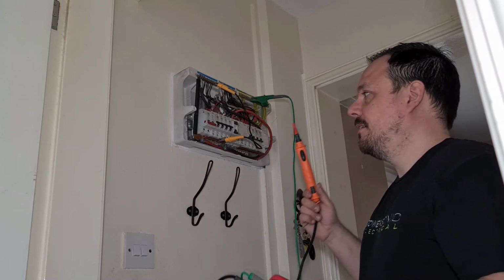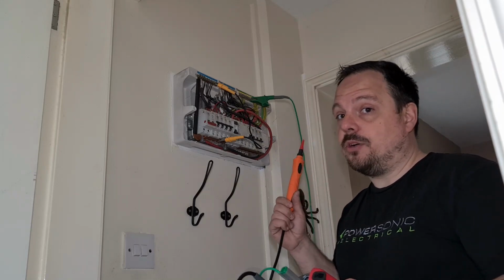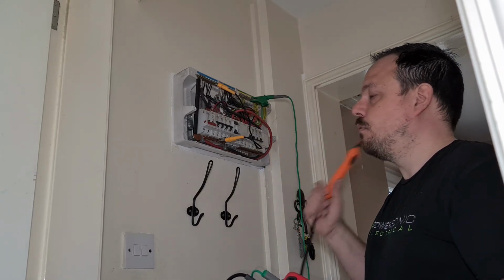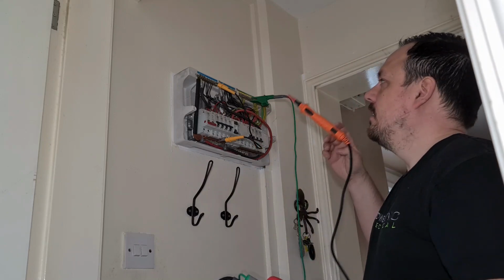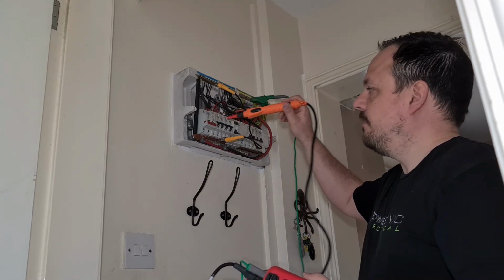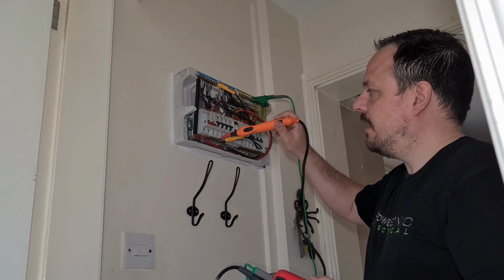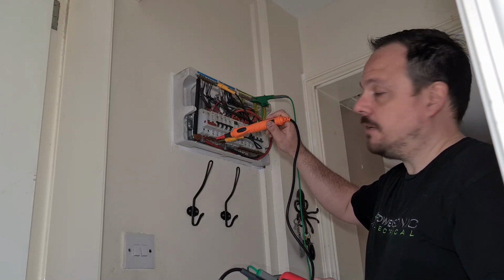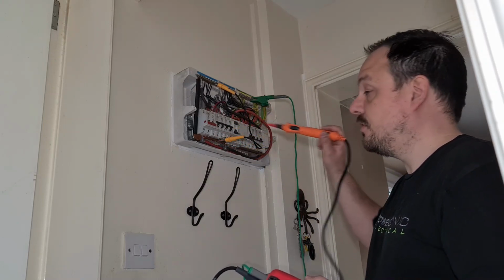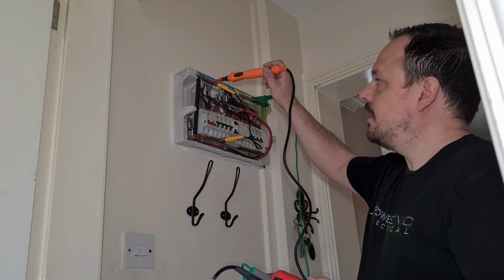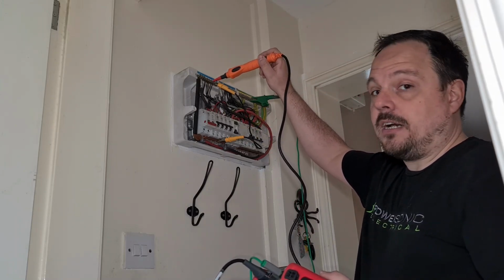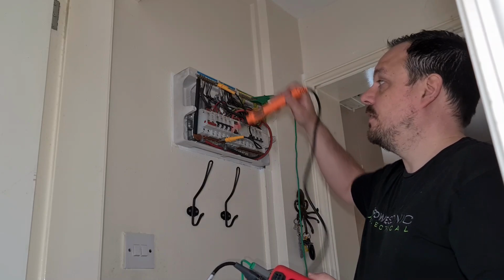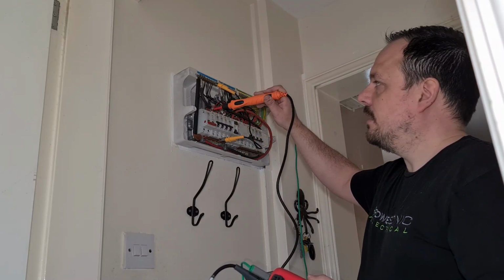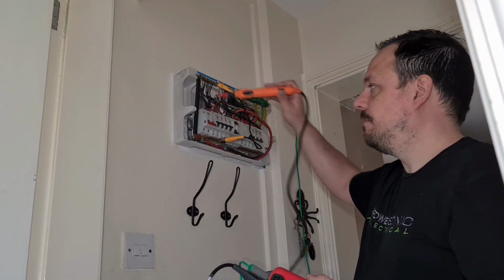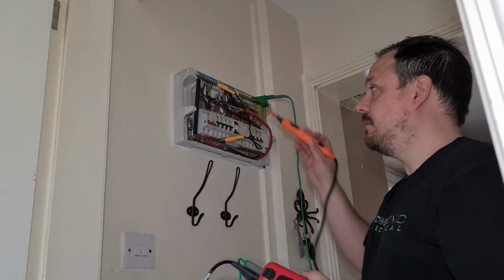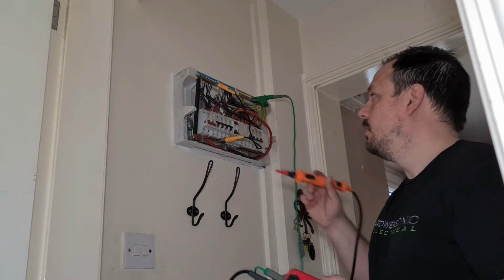That is where having a lock off away from the board you're working on is absolutely brilliant, and that's what I've got here. If we look through this, you can see what I've done. So the MCBs are in the on position, and I've got the little crocodile clip on the bus bar down here, just for those circuits. This is a split load board, and I've attached that onto the neutral terminal bar for those final circuits as well, joining the lines and neutrals together quickly and simply without interfering with any of these terminations, which is great.